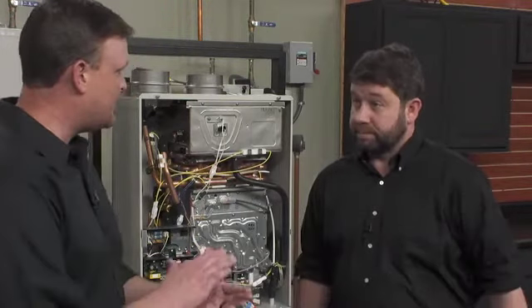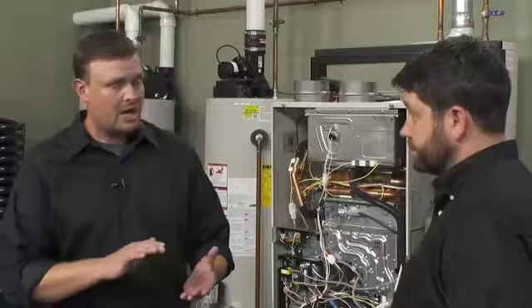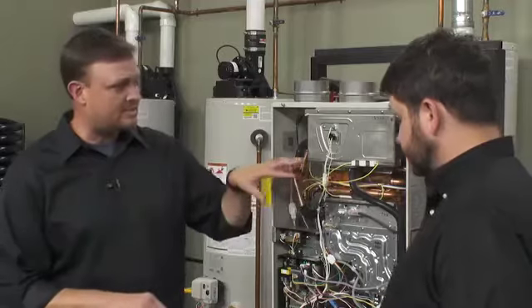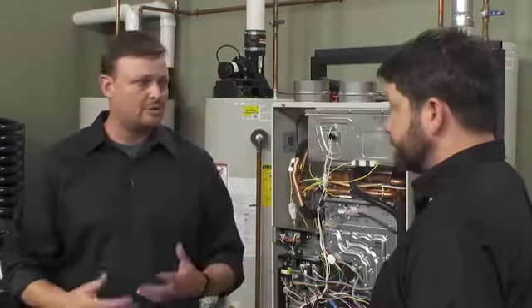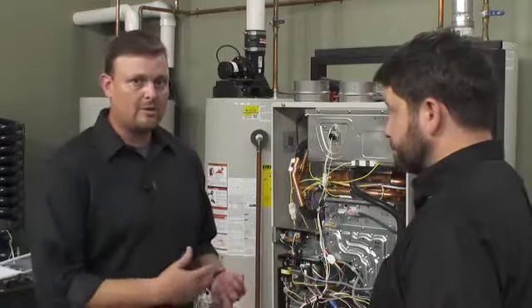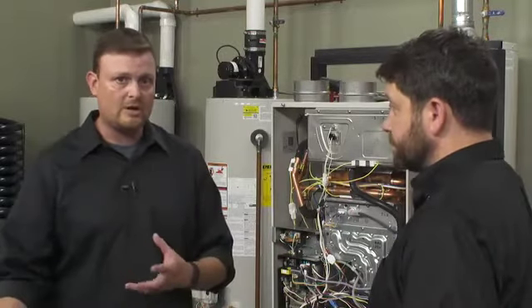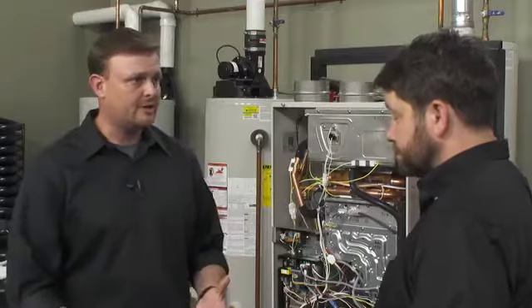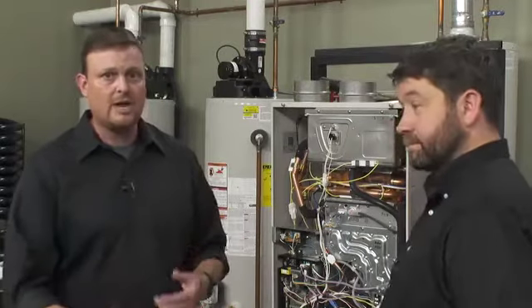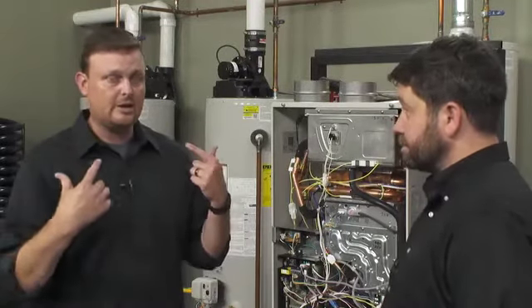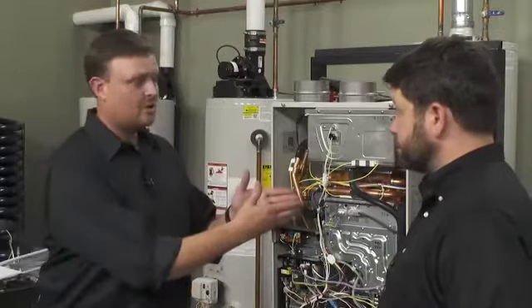Okay, so that's a 711 error code, and that's telling us that one of these safeties is open, and that's when you don't hear the clunk, clunk, or the three sets of clunks whenever you turn the water heater off or turn it back on. So if you're experiencing a 111 code or ignition failure, you're going to turn it off, turn it back on, and then you're going to use your ears. You're going to hear it. If you don't hear it, go to those safeties.